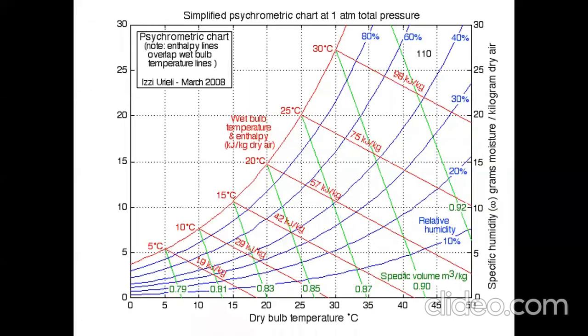Now what we will do, we will plot our points here. First was the dew point, that is 18. We have plotted it here on this 100% relative humidity curve. Now from here we will draw a line towards this y-axis. So this is our humidity. Now from 25 degrees, which was our room temperature, we have plotted this point on this line. So now this gives us our percent relative humidity. From this graph you can see the percent relative humidity was 60%.